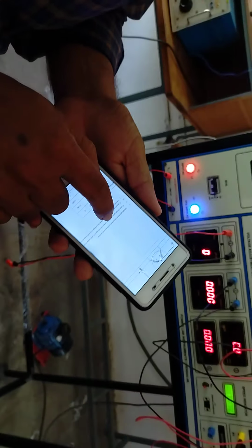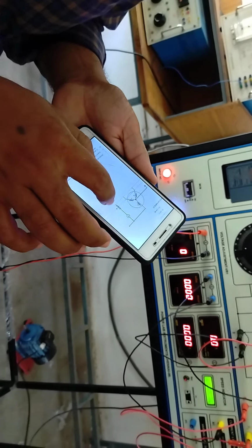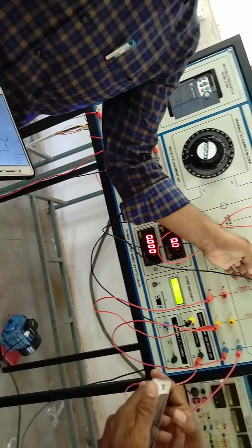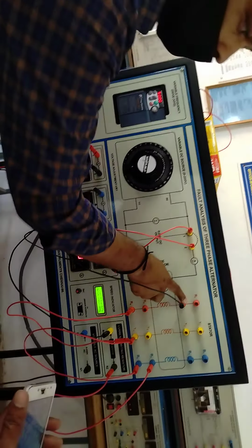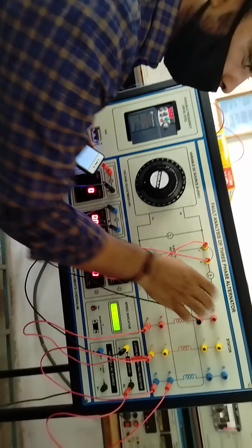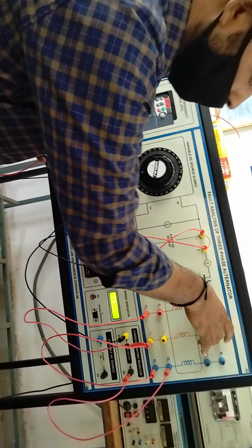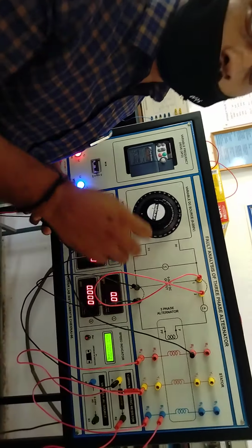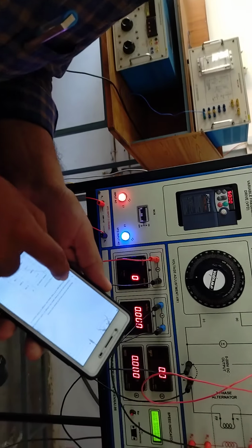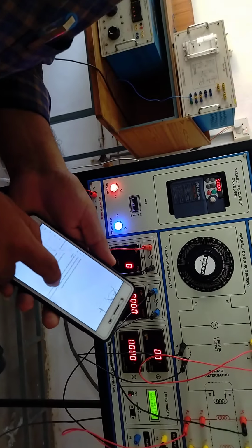Again you see it. This is the LL fault here. Short circuit the ends of two phases. Here you are creating the LL fault, the R and Y. Here R is the first phase, with 120 degree phase shift: R is first, Y is second, B is third. Likewise, you are creating the LL fault across R and Y, and R is your reference for taking the voltage. Here an example is also given: if the short circuit pair is YB, then take the voltage at Y.